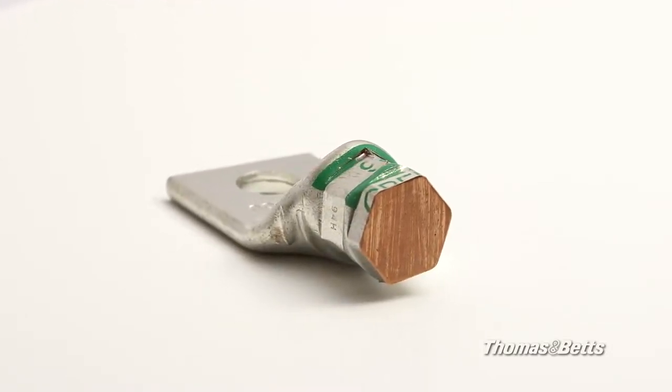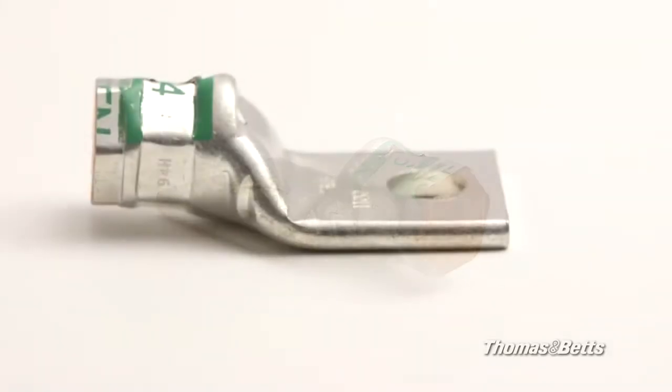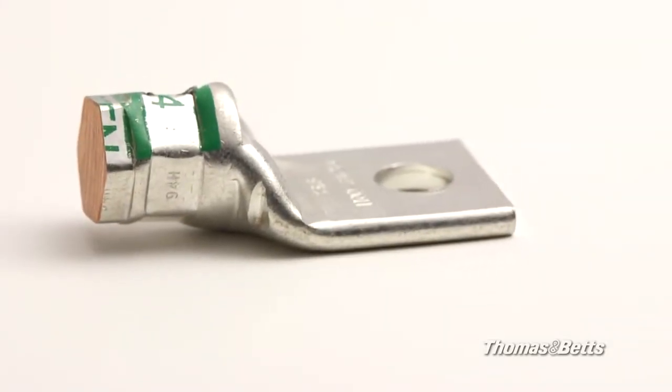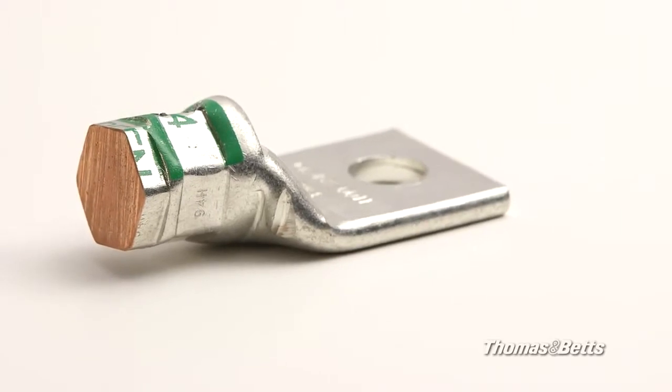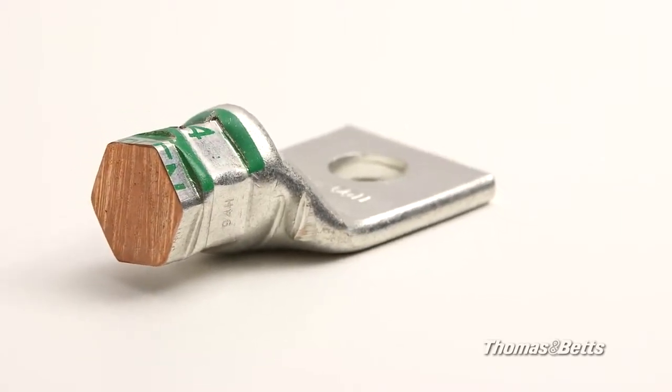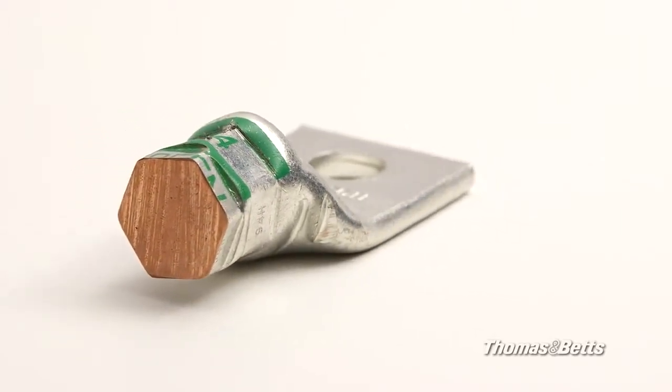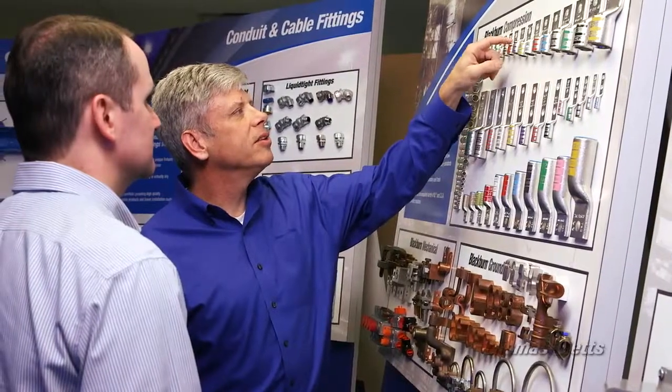The dies are designed to produce a circumferential hex-shaped compression rather than a simple indent. The circumferential compression creates a large area of high pressure, which is ideal for a low resistance ground path. Compression is especially important for data centers which are sensitive to grounds and demand continuous operation.